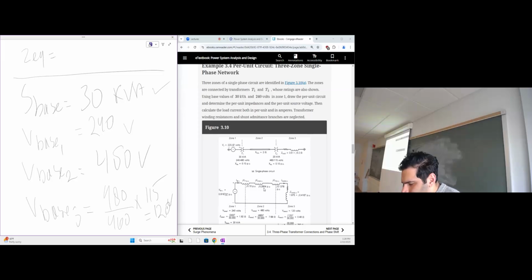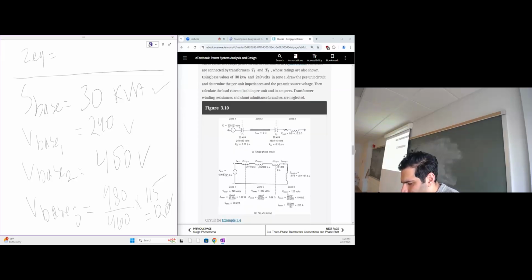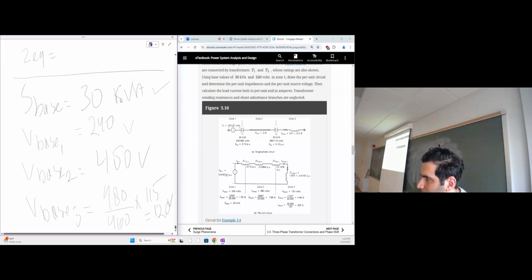Okay. I see here he got the same calculation. V base 3 is 120. Now, we got the V base 1, V base 2, V base 3. Z base 1 is now easy. V squared over 30,000. Don't put 30, multiply by K. Z base 2, 480 squared over 30,000. Z base 3, 120 squared over 30,000. S base is the same everywhere.